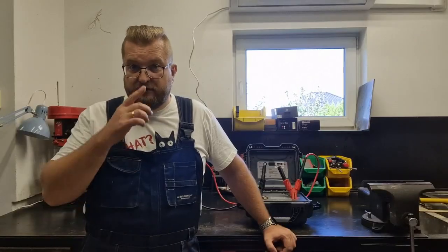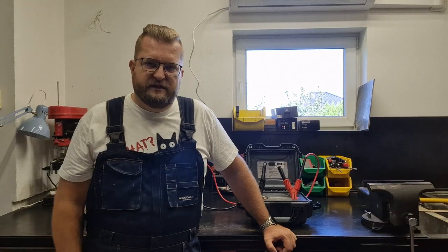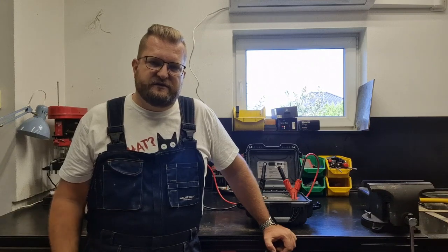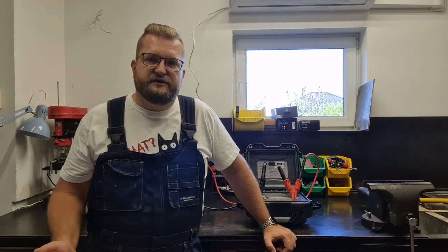First of all, what do we do this kind of testing for? Of course, we can do only the measurement of the resistance, but sometimes the resistance value is good enough to decide that some object is in good shape. But inside the insulation some phenomena happen which indicate that sooner or later this insulation will be damaged.